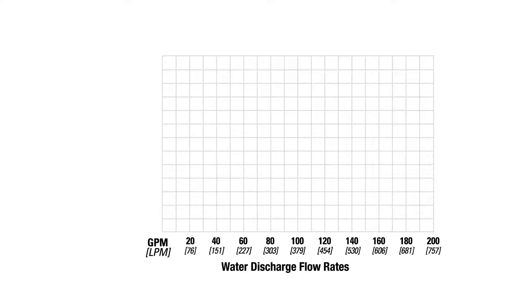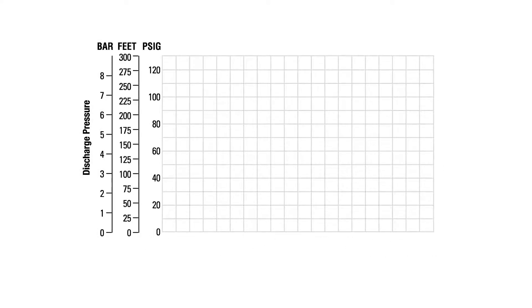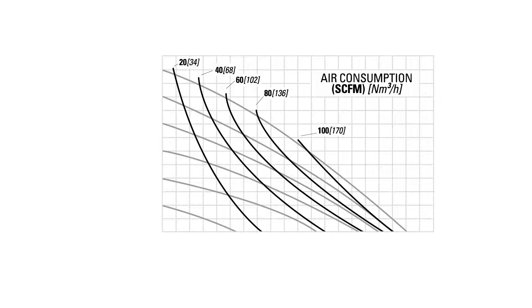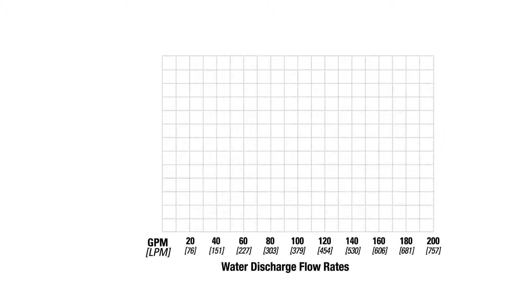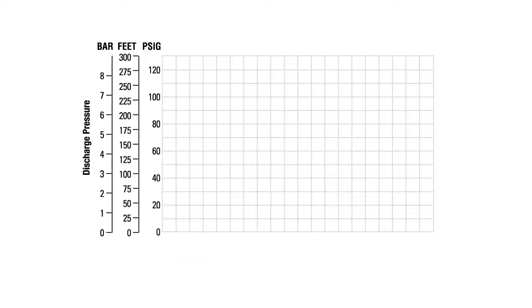A horizontal axis, a vertical axis, and a curved axis. The horizontal axis represents the pump's discharge flow rates in gallons per minute or liters per minute. The vertical axis represents the pressure, which in an AODD pump can correspond to two parameters: air inlet and outlet pressure in PSIG and bar, or the total head in feet.